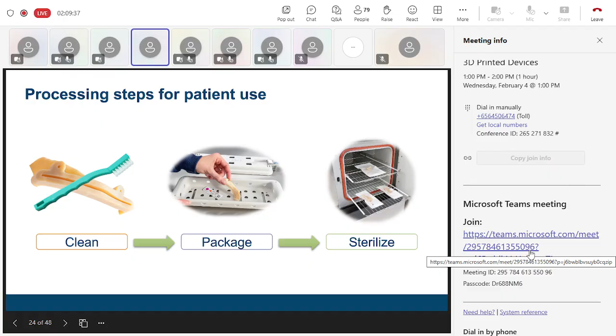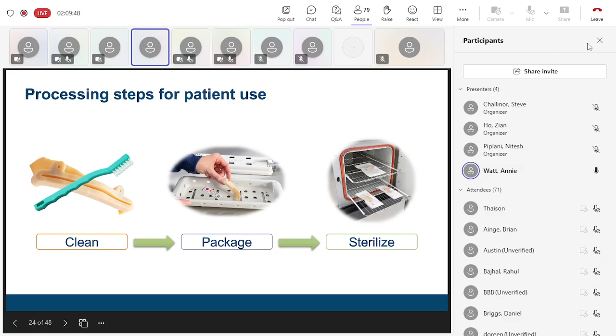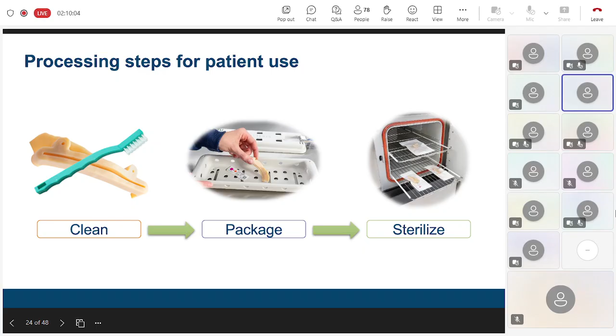The cross-functional implementation team must work together to identify the process, the equipment, and the consumables necessary for each step in the process. And once identified, each step must be validated to ensure that the specifications are met and the facility can reproduce those specifications every time they have to reprocess a 3D printed medical device. So, process validation. In cleaning, we have to demonstrate that the cleaning process can remove the expected contamination on the device without leaving cleaning chemistry residuals or endotoxins. The process must also be compatible with the material that the 3D printed device is made of.